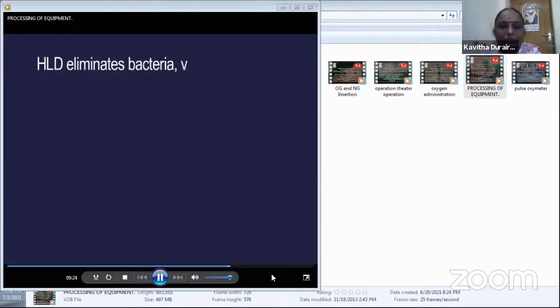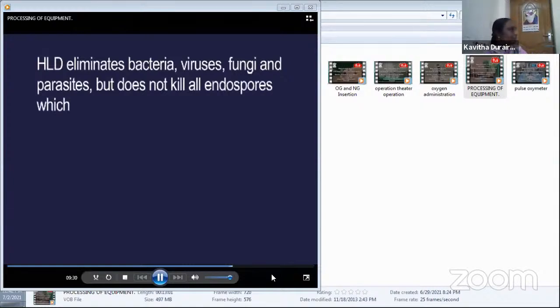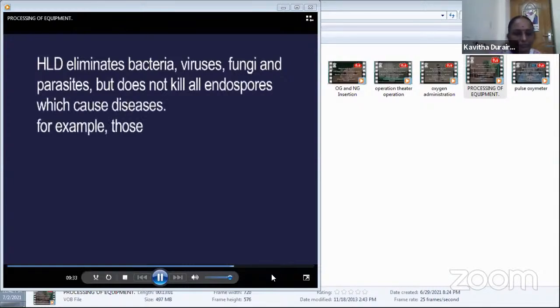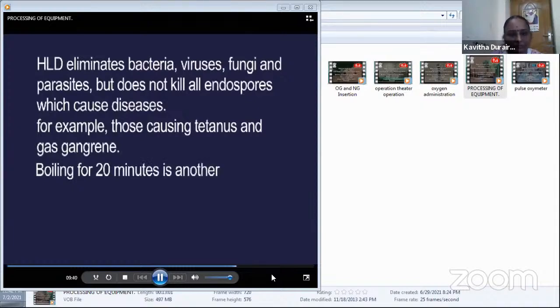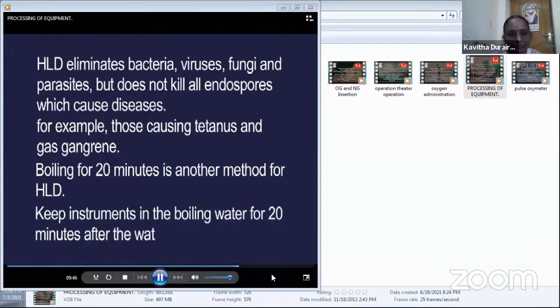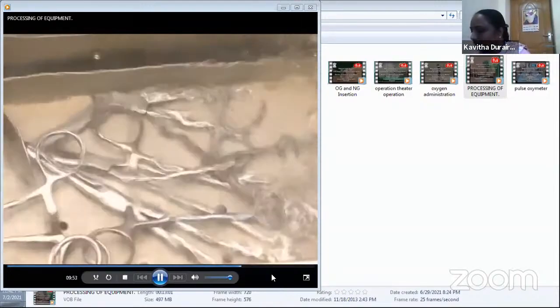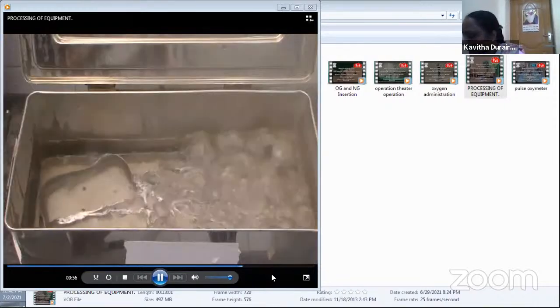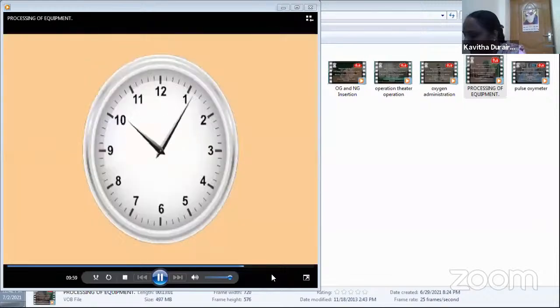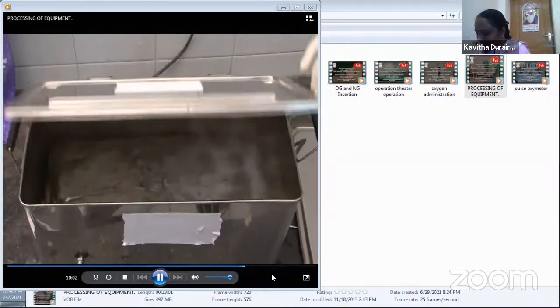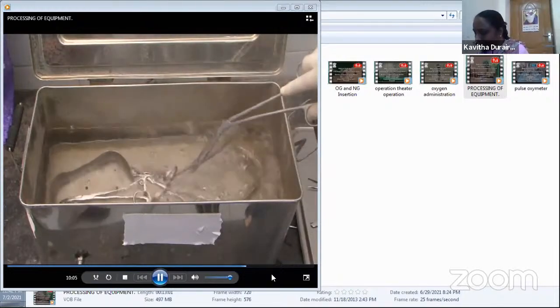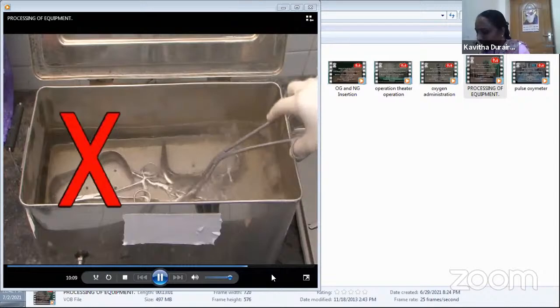HLD eliminates bacteria, viruses, fungi, and parasites, but does not kill all endospores, which cause diseases, for example, those causing tetanus and gas gangrene. Boiling for 20 minutes is another method for HLD. Keep instruments in the boiling water for 20 minutes after the water starts boiling. Please ensure instruments are completely immersed in water. The lid of the boiler should remain closed throughout these 20 minutes. Do not remove or add instruments or water during this period.